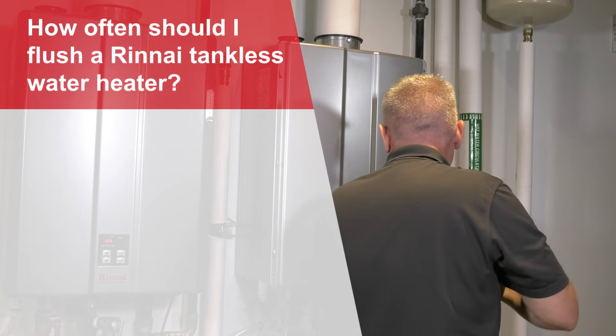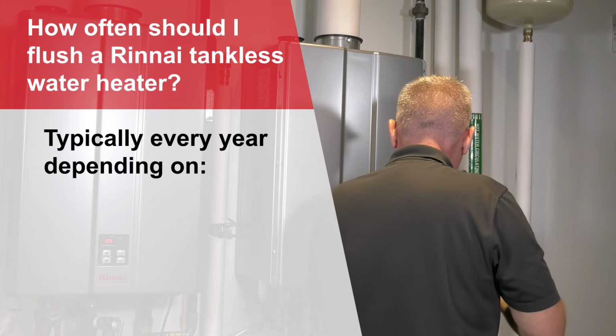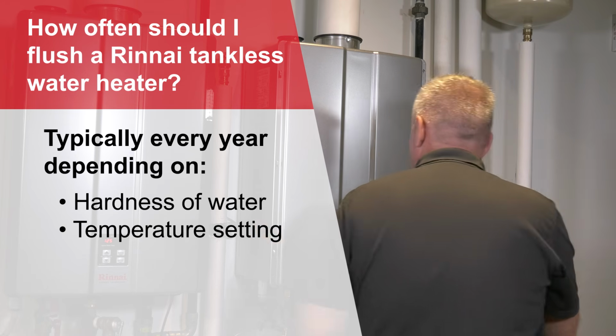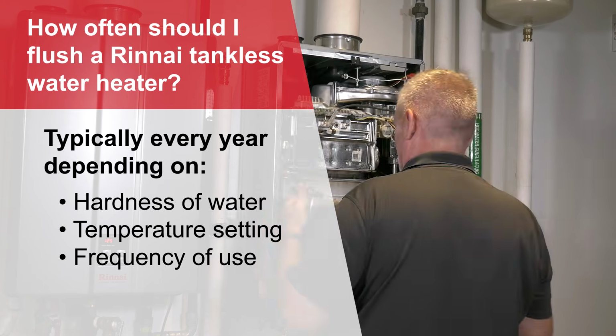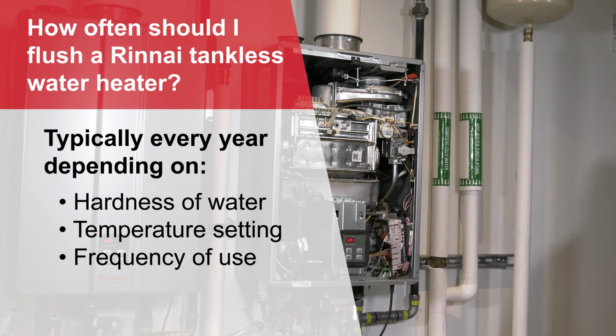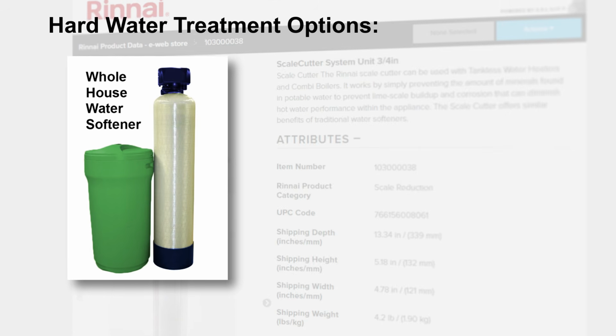Now, while the general rule is annually, this could be more or less depending on the hardness of the water, the temp setting, and the frequency of use. Now, if you'd like to reduce the frequency of flushing, consider a whole house water softener or Rinnai's scale cutter accessory.